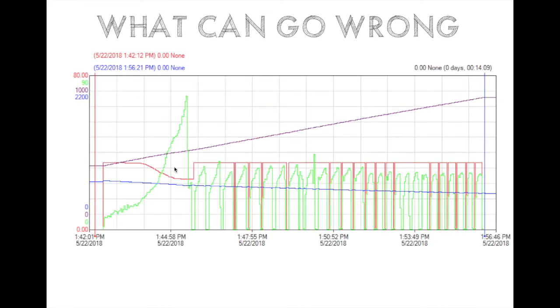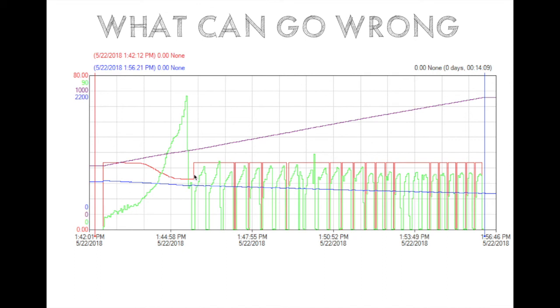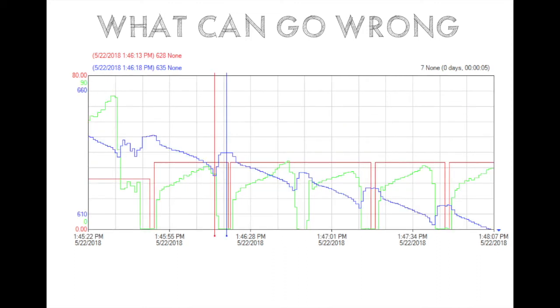Another example is kind of a restriction to flow. The red is the mass flow rate. So the flow rate is decreasing and the green is the screw speed is increasing. It looks to be uncontrollably and eventually something happens and it goes into a state that is not gravimetric mode. I can't say exactly what is happening, but it is not desirable for the process.